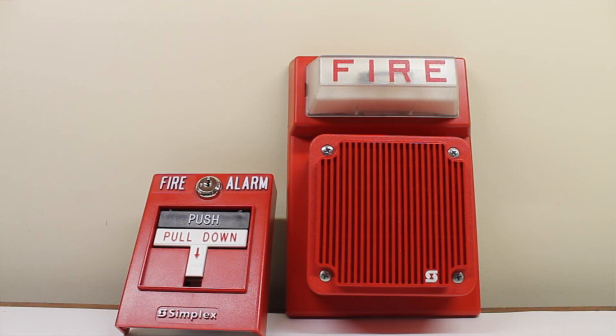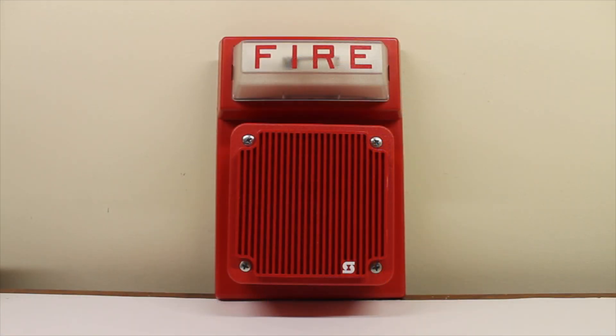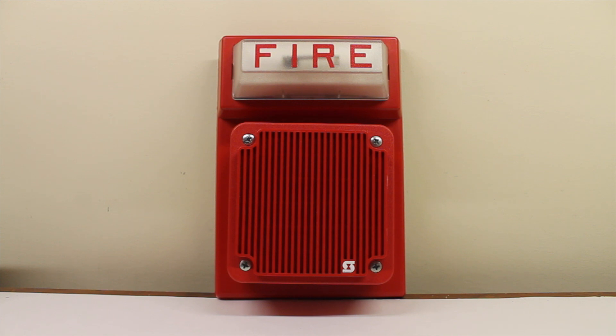If I just reset the pull station, the strobe would keep going until the panel actually resets. However, this is just my simple test setup and the strobe stops immediately as I cut power to it. Now for the grand finale, I'm going to speak into the microphone and my voice will come out of the fire alarm speaker. We'll do an all-clear announcement: 'Attention all building patrons, the fire alarm test is now over. Please resume normal activities and respond to any alarm from this moment forward.